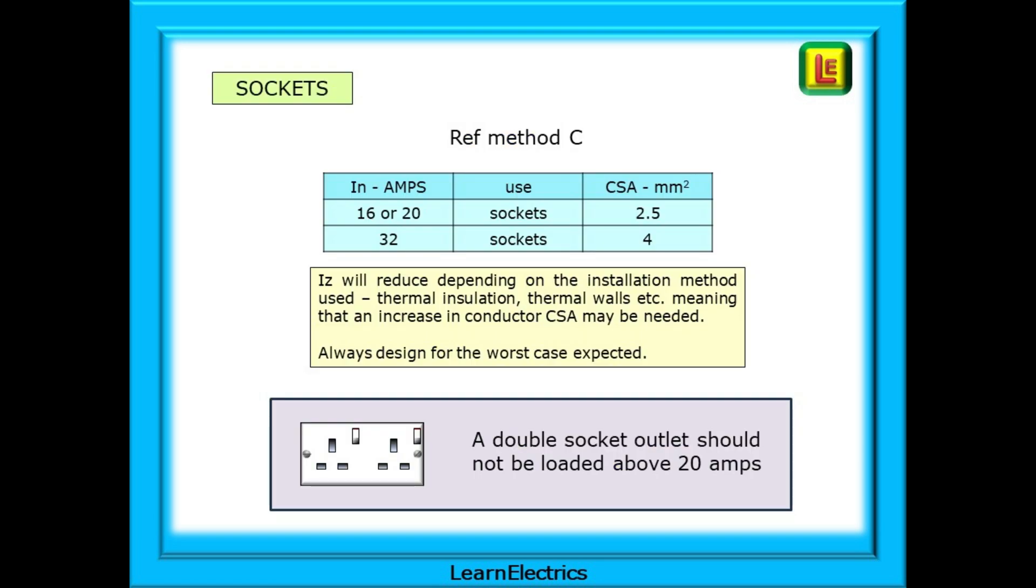We can look at sockets now. This is what we are asked many times. Can I add sockets? Can I add lights? There are usually two cable sizes of interest to us, 2.5mm² and 4mm². 2.5 cable can be protected by either a 16-amp or a 20-amp breaker, with 4mm cable being protected by a 32-amp breaker. This is for reference method C, clipped direct, and IZ, the cable's current carrying capacity, will reduce depending on the installation method used, thermal insulation, thermal walls, etc., meaning that an increase in conductor CSA may be needed in some circumstances. We should always design for the worst case expected. If the worst case is a safe circuit, then anything else is going to be safe too. And also remember that the regulations recommend that a double socket outlet should not be loaded above 20 amps.